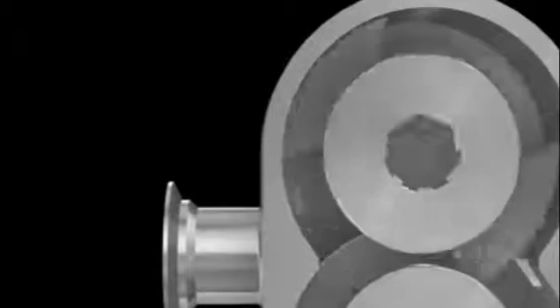In a less robust pump, the deflecting shaft and rotors strike the pump housing with every revolution. This continual rubbing wears not only the rotors but the internal surfaces of the pump, increasing its clearances.